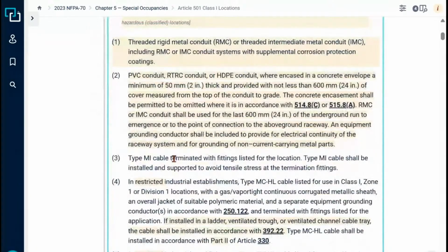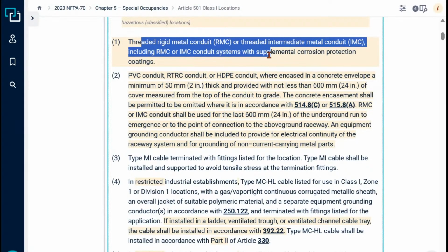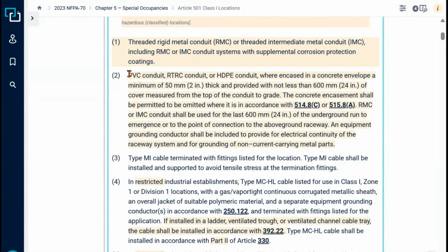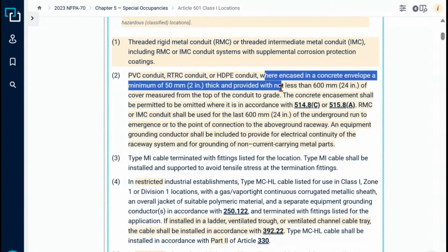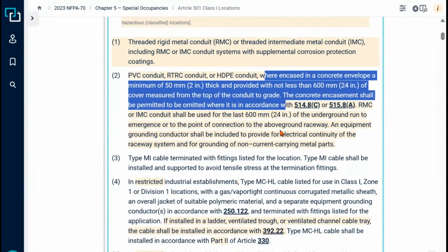So what you didn't see us talk about is this was the rigid stuff here, okay? IMC and RMC. And you also see that it's PVC conduits, RTRC, HDPE, but it has a caveat. It says where it's encased in concrete of 2 inches thick, provided with not less than 24 inches of cover measured from the top of the conduit to grade. So there are some caveats here.